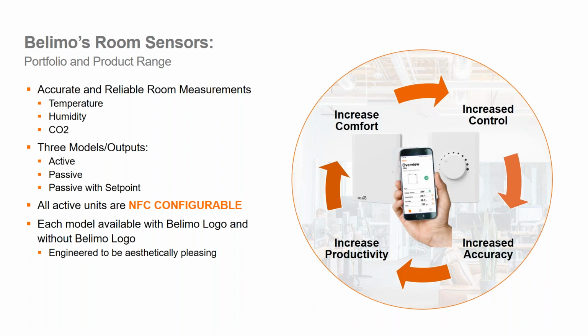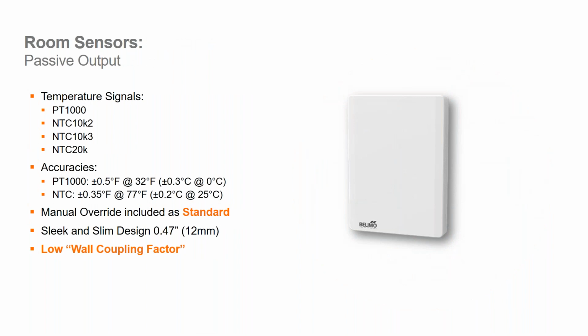The wall modules are available with or without the Belimo logo. And what you'll see is these are really nice looking sensors. They're small, they're thin. The override button is hidden on the side. So they're very unintrusive, especially if you mount them in an occupied space. A standard active or passive wall module without a set point dial is hardly even noticeable. It's thin, slim, has a low profile, and is just a very aesthetically pleasing sensor for wall mount applications. When it comes to the passive outputs, of course, we cover the gamut: PT1000s, NTC 10K type 2 and 3, the 20K NTC. The accuracies of the PT1000s are plus or minus 0.5 degrees Fahrenheit.